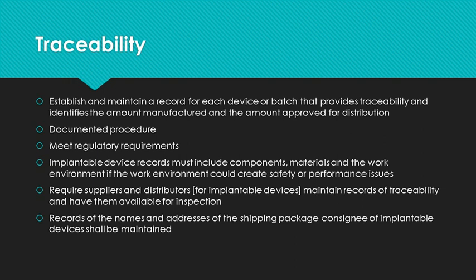Traceability has been mentioned in several other videos. The requirements of ISO 13485 are straightforward: your organization must establish and maintain a record for each device or batch, providing traceability to materials and components through the manufacturing process and to the delivery consignee. You must document how traceability will be performed in a procedure, and your procedure must meet regulatory requirements. You must record the amount of manufactured product and the amount approved for distribution.